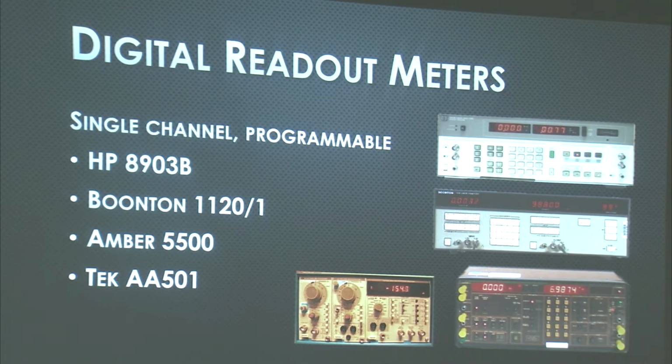The one below it is the Boonton, and that exists because Boonton was losing sales to HP, so they went and created an equivalent product, and it's very equivalent. The circuitry is pretty similar, in fact. It's easier to work on, and there's information. I've even posted information on how to hot rod one of those.